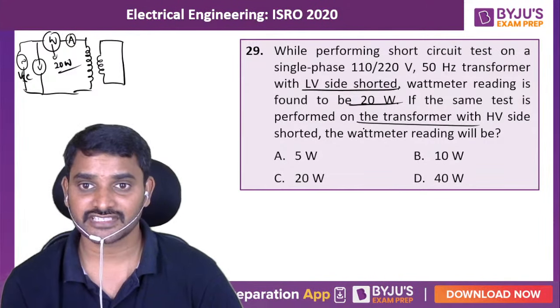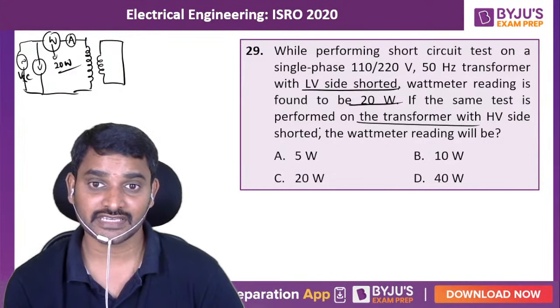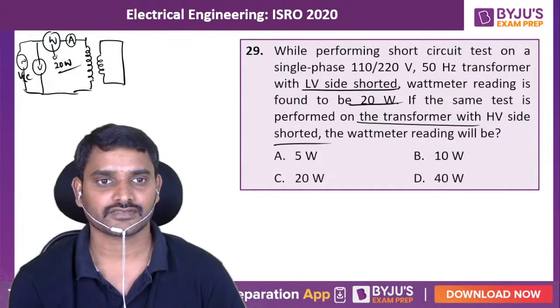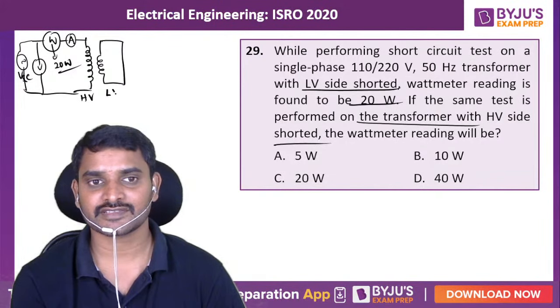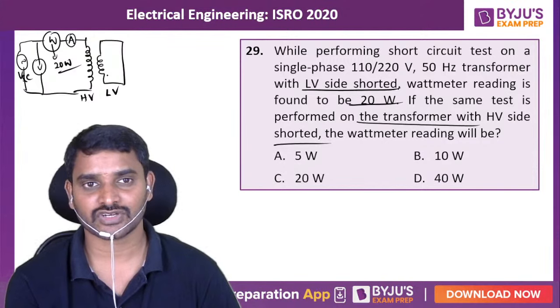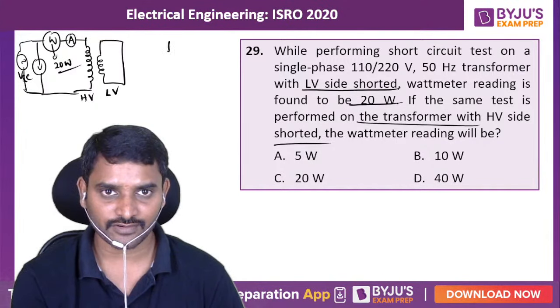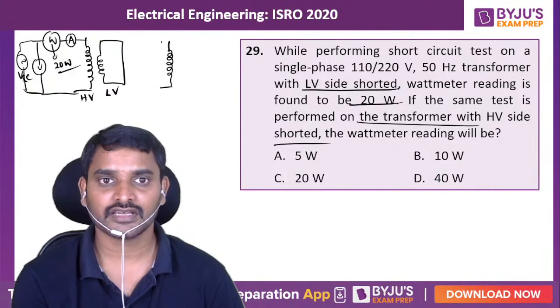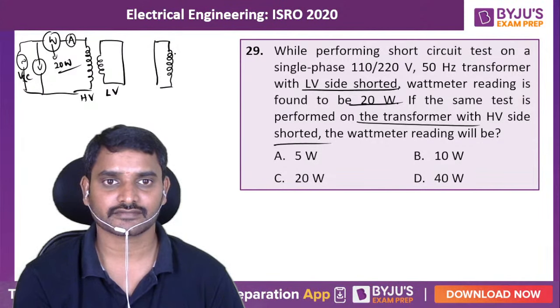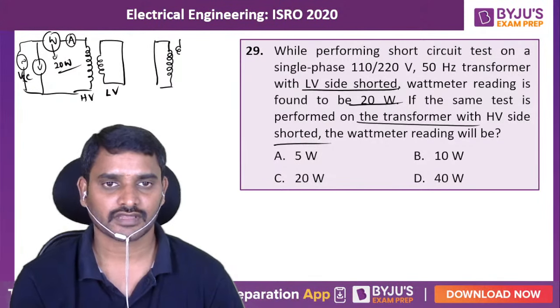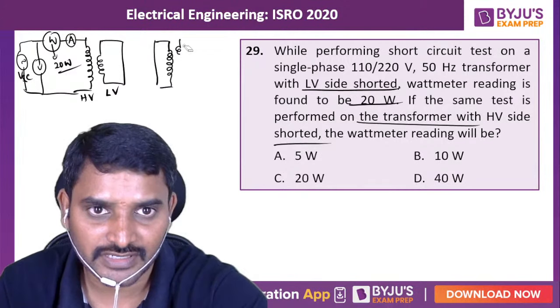If the same test is performed on the transformer with HV shorted, so this is my high voltage winding and this is my low voltage winding. Here low voltage winding is short circuited. If I short the high voltage winding, what could be the wattmeter reading? He is asking. What will be the wattmeter reading? He is asking.